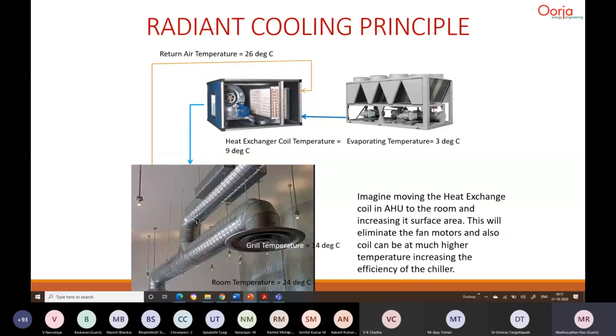So the heat exchange has to be very rapid. Within less than a second, the air will go from 26 degrees centigrade to, let's say, 14 degrees centigrade. To maintain 24 degrees centigrade, typically we supply 14 degrees centigrade air. So for such rapid heat transfer, of course, there has to be a significant temperature difference, right? Only then there will be a rapid heat transfer. That's why you need very cold water at 7 degrees or so. The coil temperature on an average is 9 degrees centigrade. So this is how it works.